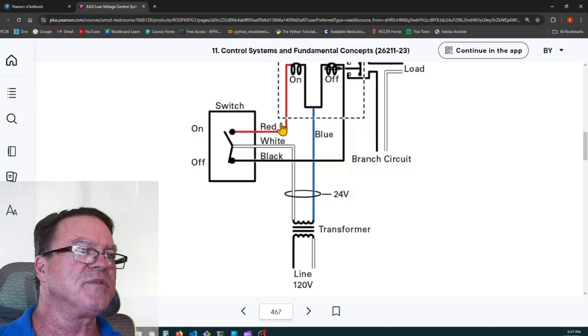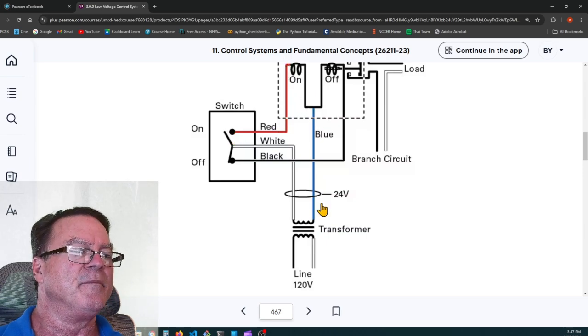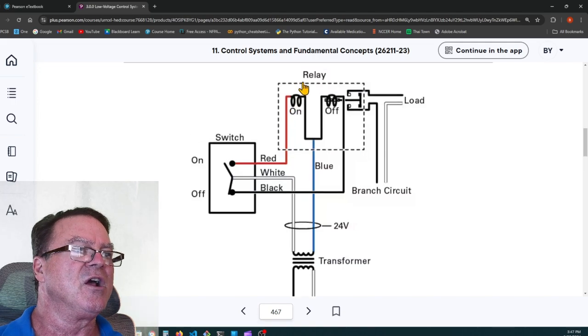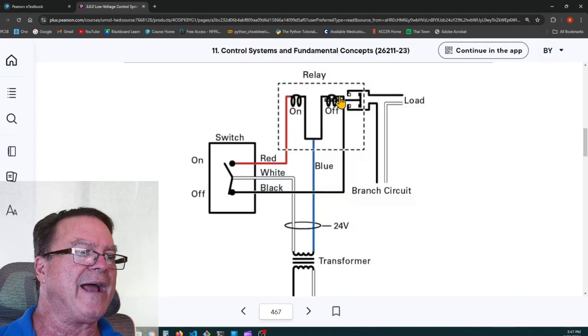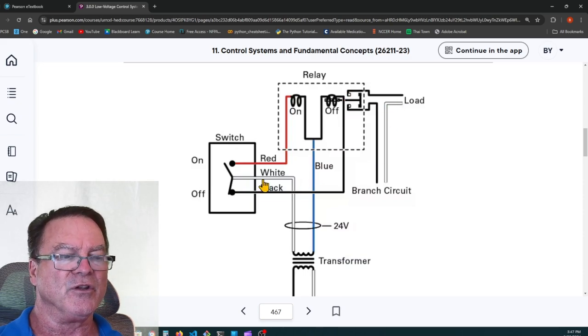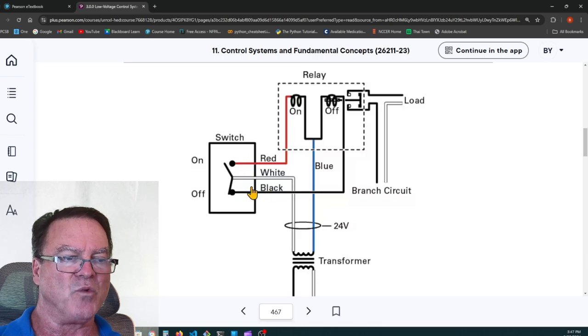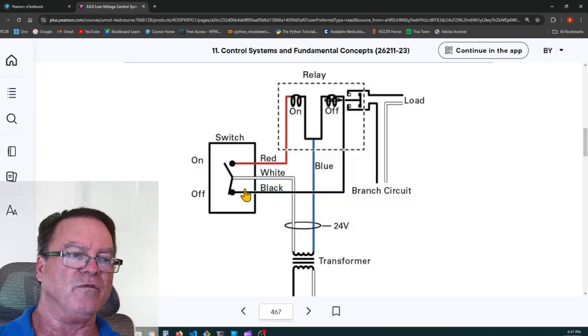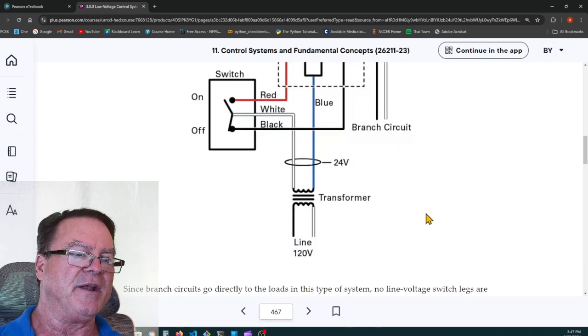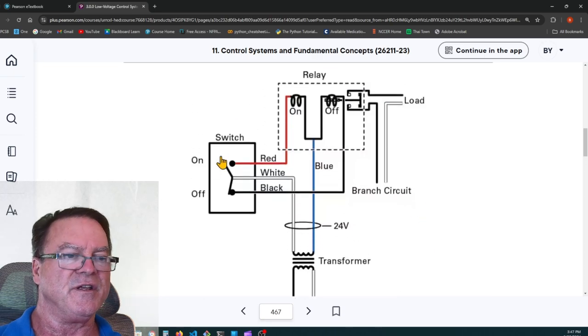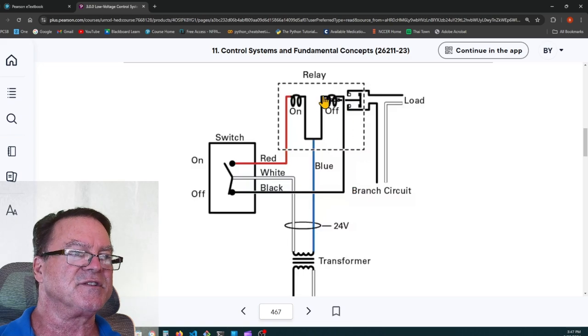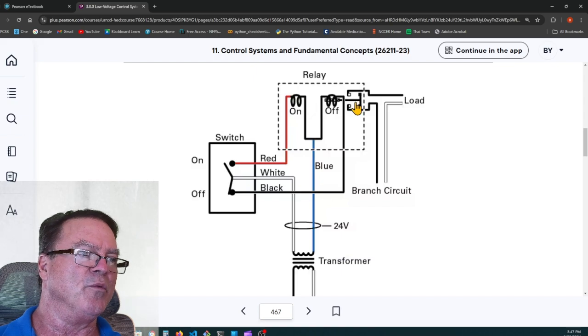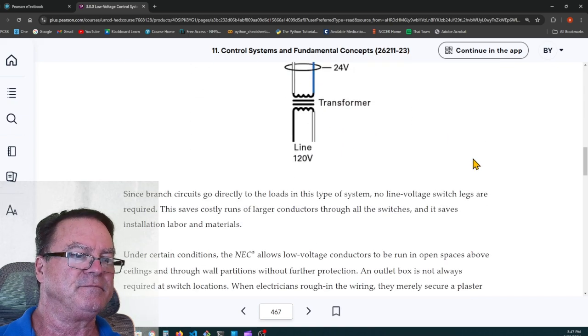When you turn it to the on position, the red side of this is energized, causing this plunger to be pulled out, closing the contact, turning the lights on. But remember, the low voltage signaling part of it is what we're concerned with. It's low voltage, so it's not dangerous. And when you want to turn it off, you turn the switch the other way. Now you've energized the black wire, and it allows the plunger to be pulled back and disconnect the lights.